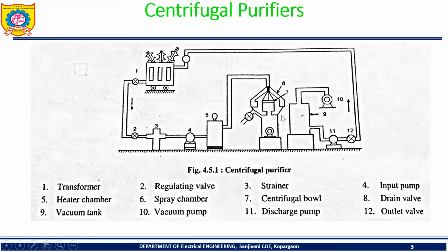This oil is then shifted to another tank called the vacuum tank. The vacuum in that tank is maintained by means of this pump, which is called the vacuum pump. Again, it is an electrical pump. After this, the oil will be discharged to a discharge pump, because as the pressure is very low, we have to increase the pressure to get this oil extracted toward the transformer tank. So this is the overall construction.